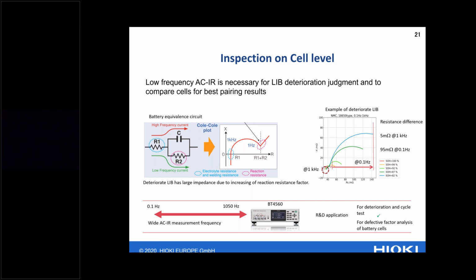Compared to a lead acid battery, for lithium-ion batteries you need to measure across the frequency bandwidth, because the characteristics can't be measured at fixed frequency points - they need to be done across the range, starting from 0.1 hertz up to 1 kilohertz.